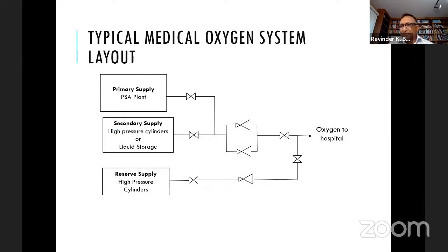Most standards recommend there should be three sources of supply. Specifically, when used in hospitals for supporting life, you have to be absolutely sure oxygen is available at all times. They recommend, and these can be combined in certain ways, that there should be a primary supply of oxygen. It's not only oxygen, all medical gases connected to the hospital pipeline should have three sources of supply: a primary supply, which can be a PSA plant, a secondary supply, which can be high pressure cylinders or a liquid tank, and then a reserve for a very big emergency.